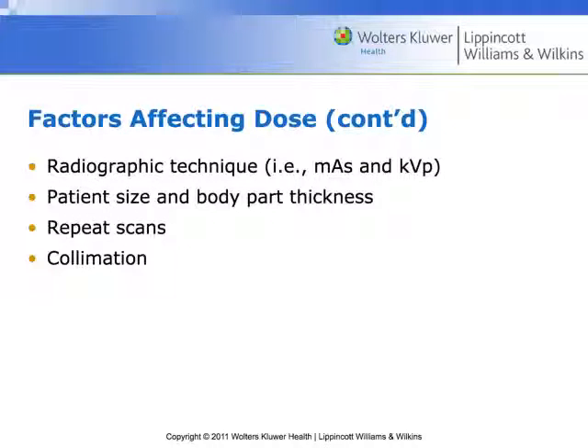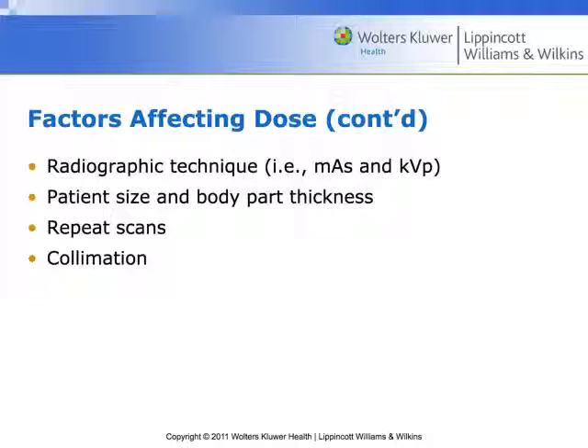We do have some control over radiologic technique. With CT, we don't have a lot of control over kVp — we'll typically use 120 or 140 kVp. For mAs we have more control; a lot of times we give it to the automatic tube current modulation, setting a range, and it modulates between those ranges as needed. One thing we don't control is the patient's size, part thickness, or the density of that part.